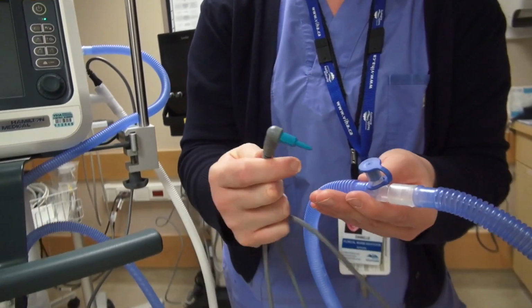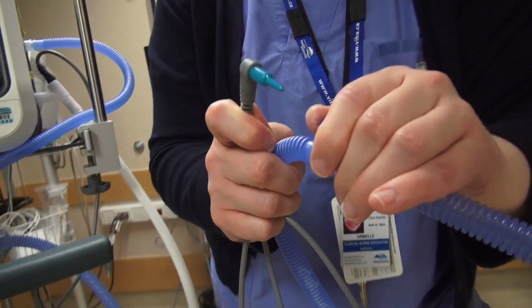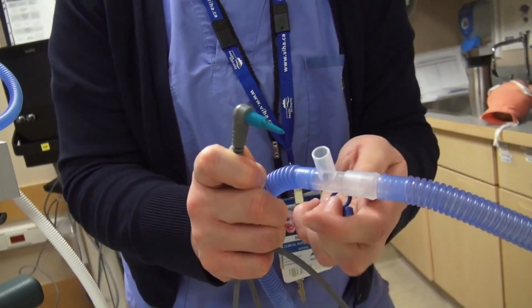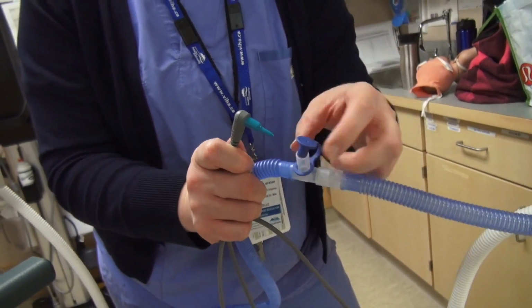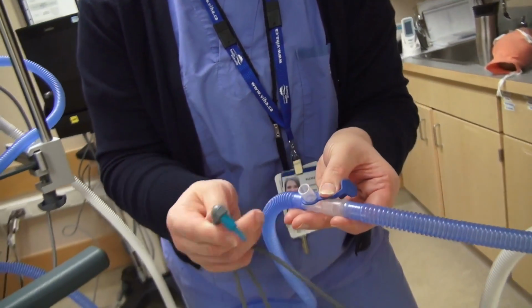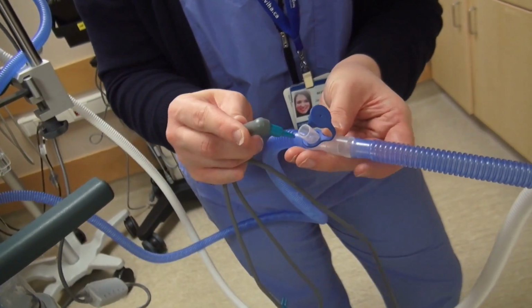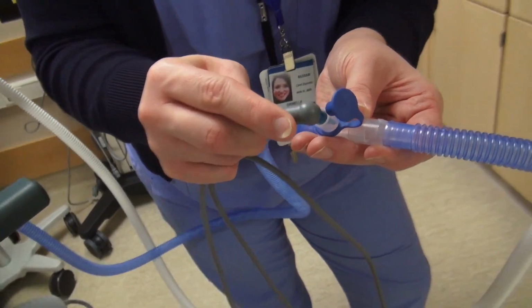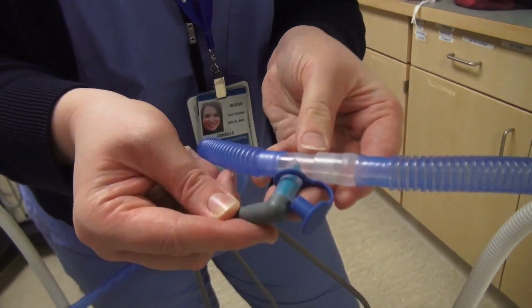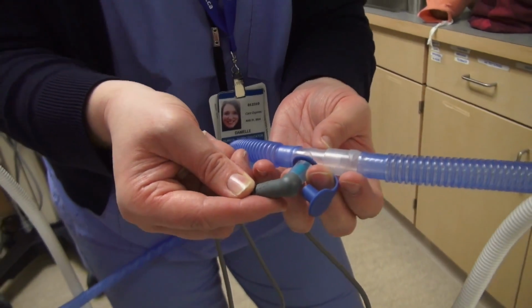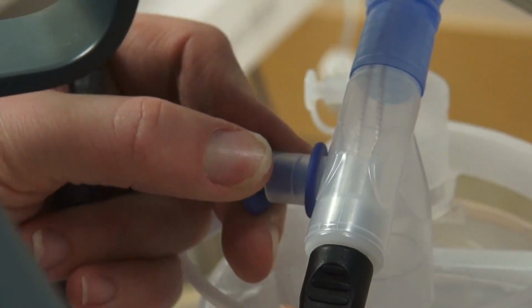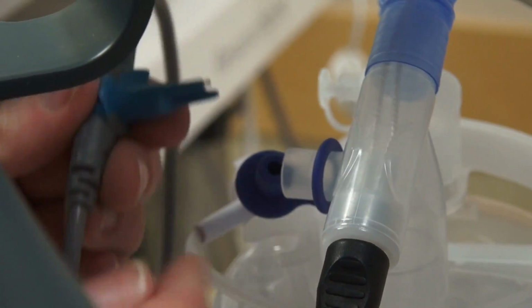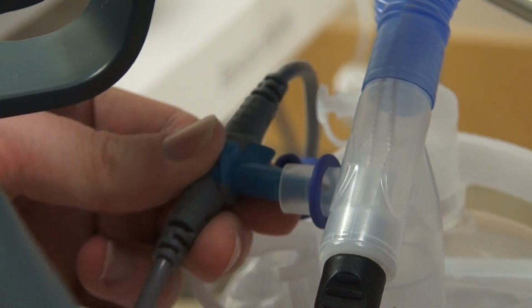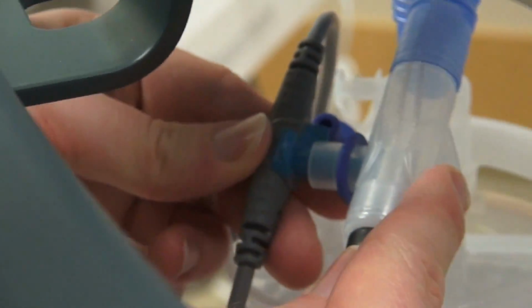Step 4. Attach temperature probe at the end of the blue inspiratory wire to the lowest port on the blue inspiratory tube closest to the patient. Step 5. Attach the 2-prong probe from the blue humidifier wire into the humidifier port.